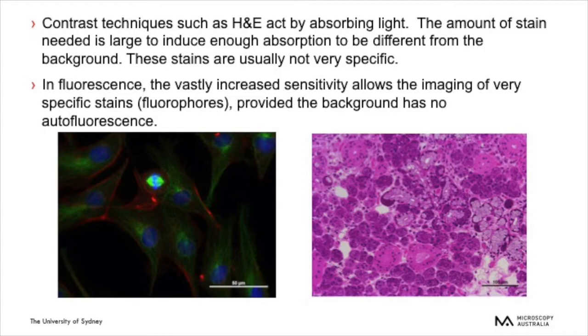For many hundreds of years, transmission light microscopy was used to observe biological specimens and a huge amount of scientific knowledge was gained. Today, contrast techniques are still very valid and valuable, with pathologists using contrast stains as shown on this slide. However, as you can see in this comparison, fluorescence vastly increases the sensitivity, allowing more specific staining of proteins and organelles. The contrast techniques act by absorbing light, while in fluorescence we collect emitted light. It is much easier to detect emission of light than absorption of light — a dark-adapted human eye can detect tens of thousands of photons per second, but the same eye struggles to distinguish a 1% difference in absorption.